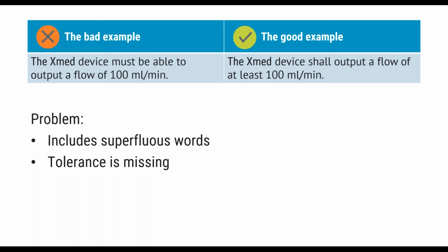So previously, I said that medical device professionals often miss training in this area. This is also true for the notified body auditors. Thus, they are not likely to detect several of the issues that I presented to you so far. However, this particular mistake, they are going to react to probably, and they might also react if you use escape clauses, because they're going to say, well, that's a subjective requirement. So some of these things they will react to, not all. That doesn't mean you shouldn't implement the rules, obviously, but you can see some things are less likely to result in a non-conformity, but rather in a problem in the product development.